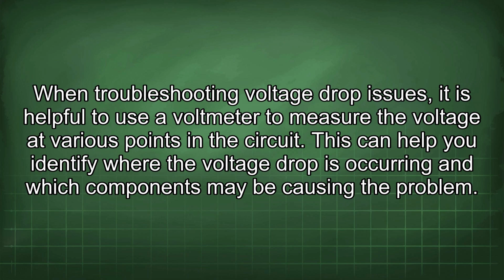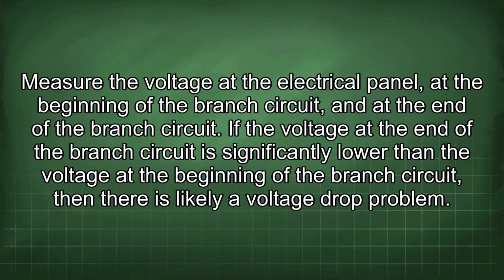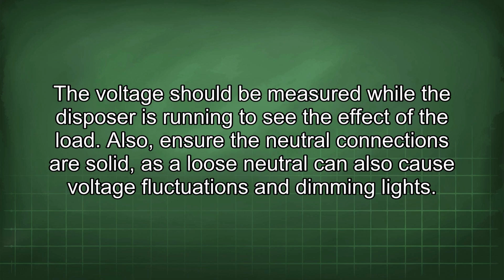When troubleshooting voltage drop issues, it is helpful to use a voltmeter to measure the voltage at various points in the circuit. This can help you identify where the voltage drop is occurring and which components may be causing the problem. Measure the voltage at the electrical panel, at the beginning of the branch circuit, and at the end of the branch circuit. If the voltage at the end of the branch circuit is significantly lower than the voltage at the beginning of the branch circuit, then there is likely a voltage drop problem. The voltage should be measured while the disposer is running to see the effect of the load. Also, ensure the neutral connections are solid, as a loose neutral can also cause voltage fluctuations and dimming lights.